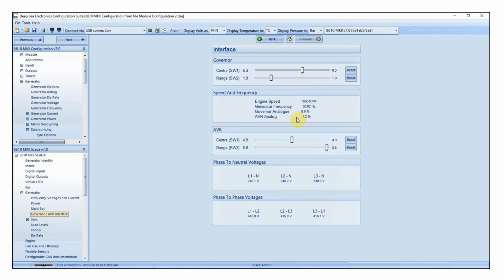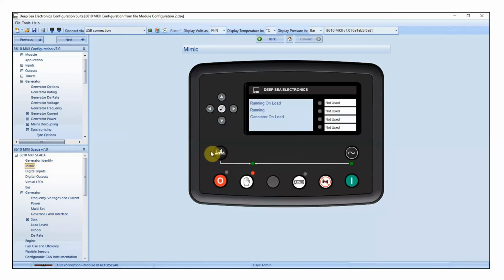Normally, you would expect to see at full load no more than 10% on your governor and AVR analog percentage, no more than 10%. However, if you have droop enabled on your governor or AVR, then we would say no more than 30% at full load. As a rule of thumb, if you are seeing more than 50% on your governor and AVR analog drive, something is very wrong. And more likely, the problem is actually caused by having the incorrect switch 1 and switch 2 settings.